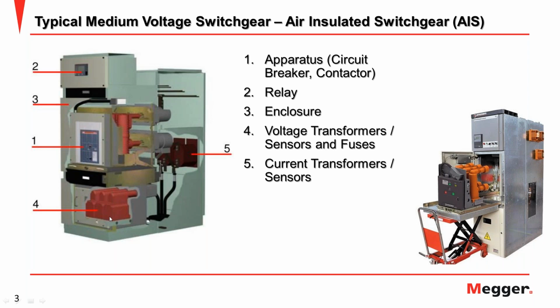Number four, in the bottom part of the panel, they mostly put the VT, voltage transformer, or sensor and fuse. And for number five, the current transformer or CT position, you can mostly see it close to the bus bar, around the cable that connects to the bus bar. Some MV switchgear may put the CT close to the VT, but in general all MV switchgear will consist of these components: relay, metering, VT, CT, and also breaker. So the breaker is a big part of the MV switchgear. This is why we need to test this part, the breaker, at maintenance time.